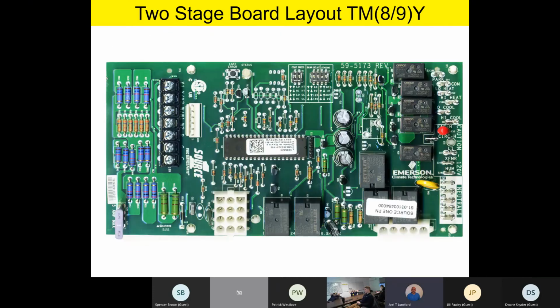So as you take a look at your 2-stage control board, now this is a 2-stage heat, 2-stage cool, and again, this board will be found on the TM8 and 9Y products. Now, it does use a high efficiency blower motor, but the neat thing about this board, it's got some really cool functions that I think you're going to enjoy when we start getting into especially some staging functions, because this board, even though it's a 2-stage heat, 2-stage cool board, it has the unique capability of allowing single-stage thermostat operation, which is really kind of neat.